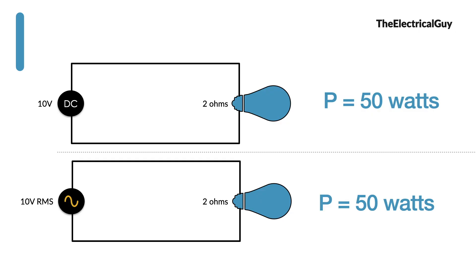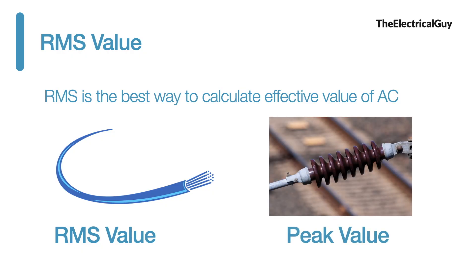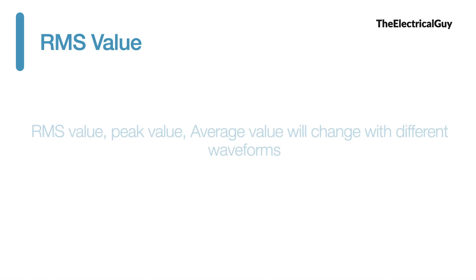RMS value is the best way to calculate the effective value of AC system. For instance for calculating size of cable considering the RMS current measurement is always helpful. But for considering insulation in high voltage AC application peak value shall be considered rather than RMS value. RMS value, peak value, average value will change with different waveforms. These values will be different for sine wave, for square wave, for triangular wave etc.